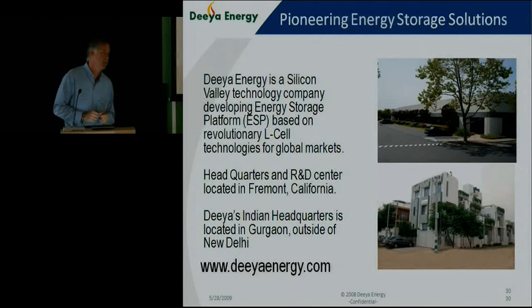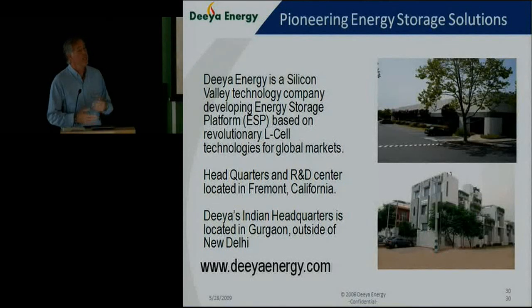So that's roughly between charging and discharging? I'm sorry, say it again? That's split equally between charging and discharging? That's the round trip efficiency. Well, most of the loss of efficiency is during the charge cycle. The discharge cycle is probably much more efficient than the charge cycle, and most of that is based on converting. Energy is lost in electronics, and we lose quite a bit in converting to the level of voltage that the system needs to push energy back into the system, as opposed to it naturally wanting to come out. Like any energy storage system, it wants to deliver, and so discharging becomes a very easy, natural thing. So putting energy into the system is less efficient than the delivery of the energy.